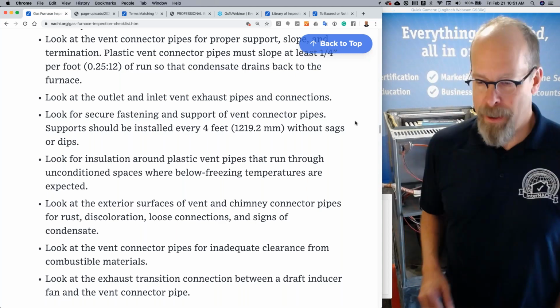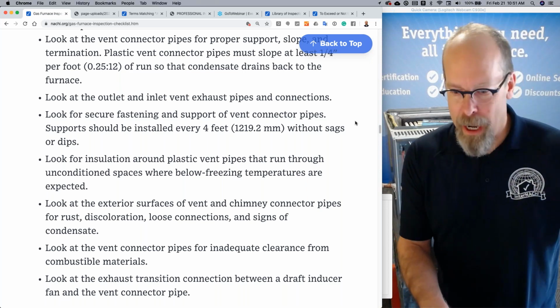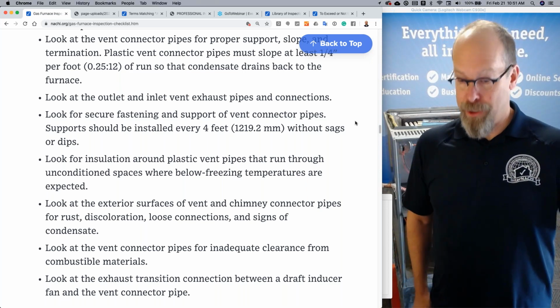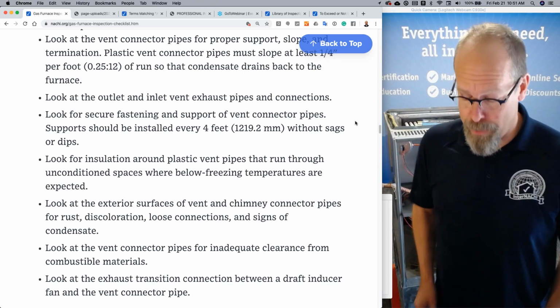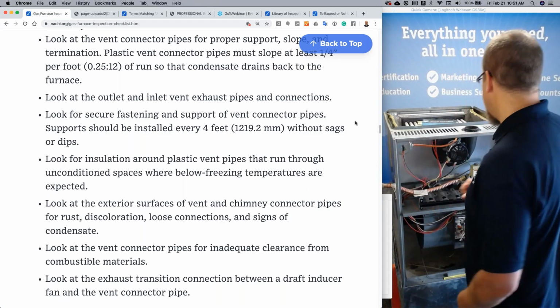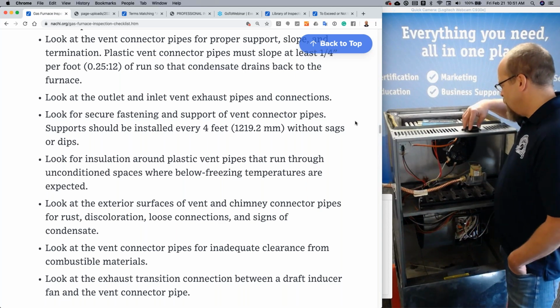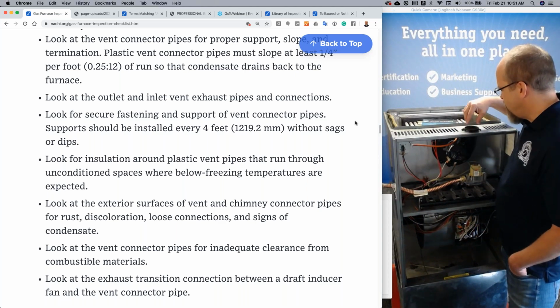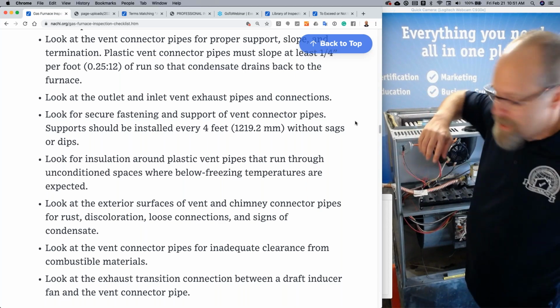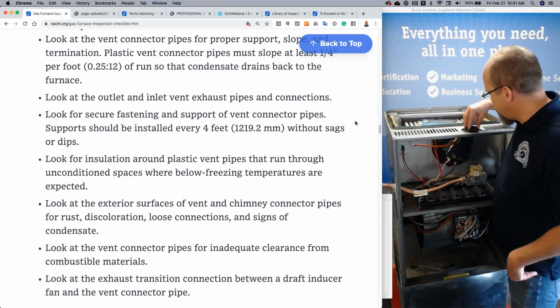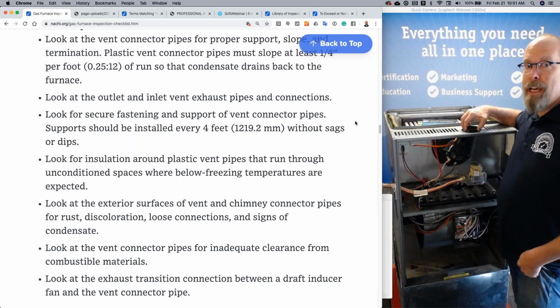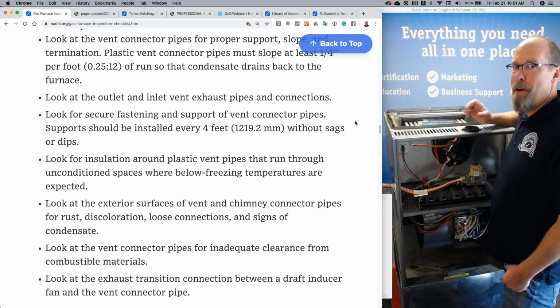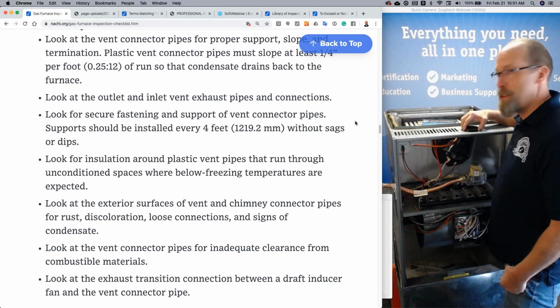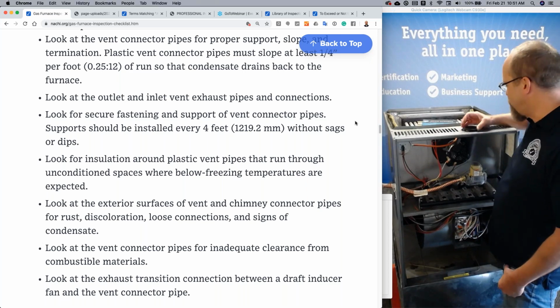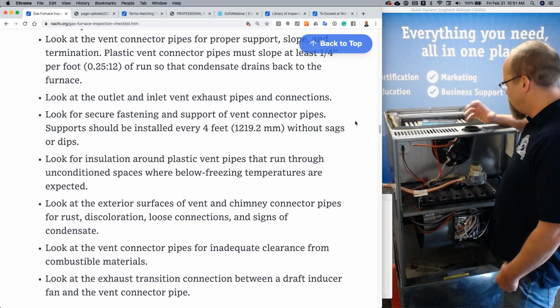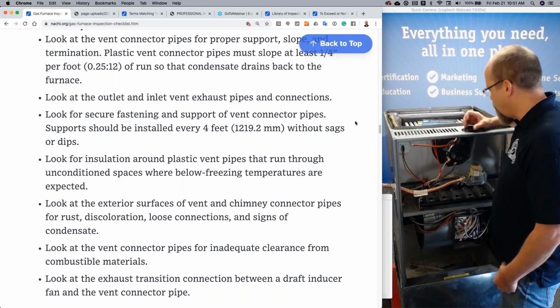We'll take a look at that in detail a little bit more. Look at the exhaust transition connection between the draft inducer fan and the vent connector pipe, excuse me. So right here, a lot of manufacturer installation recommendations say that this is really important. This connection is sometimes loose, and I tend to tug on them now. I just give it a little tug and make sure that they're fastened and secured, because if it's open or it gets bumped or is loose, there's a lot going on right here.